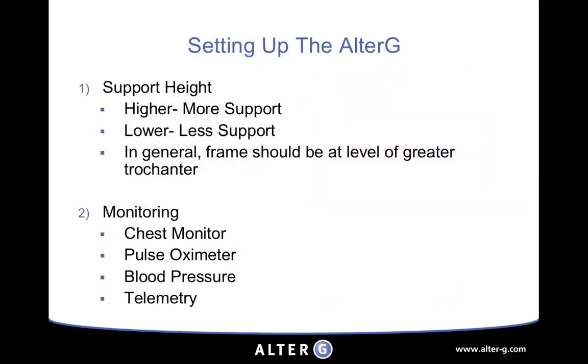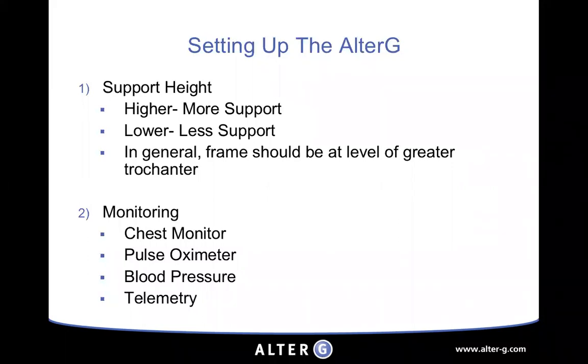Once the patient is in the anti-gravity treadmill, consider support height. The higher you set it, the more support the patient gets for trunk control; the lower, the less support and greater challenge. Generally the cockpit frame should be at the level of the greater trochanter so it doesn't affect arm swing. You can monitor patients with a chest monitor, pulse oximeter, blood pressure, or telemetry — all can be used with the anti-gravity treadmill without interference.